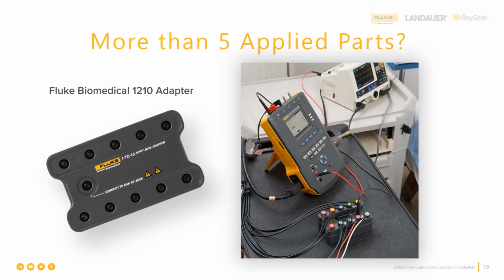Oh, and one more thing. You could use more than one of these if you needed to on the same electrical safety analyzer and medical device to run tests according to what the need may be. So it's not just one, it could be several, depending on how many patient applied parts or different kinds of applied parts, B, BF, or CF, that we need to short together.